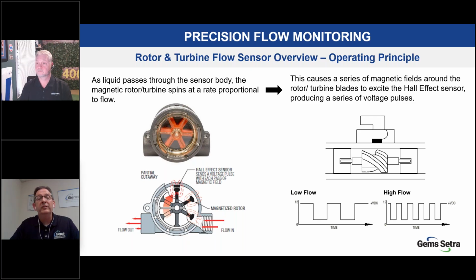Likewise, on the right-hand side, the turbine. So instead of a rotor spinning like a grist mill or a windmill, you're having a turbine spin right inside of the line, but it's also magnetic and it's also being picked up by a Hall effect sensor. As the flow rate increases, as you look on the bottom, the frequency of the output rises and it's able to produce a higher frequency of that voltage, from 0 to 12, 0 to 12. It keeps oscillating between those in the square wave form there. So at lower flow, it's a lower frequency output. At higher flow, you're getting more pulses and it's a higher frequency output. Next slide.